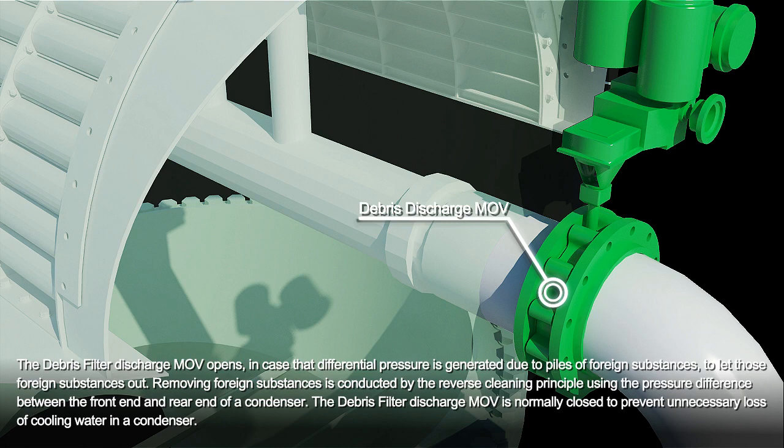Removing foreign substances is conducted by the reverse cleaning principle using the pressure difference between the front end and rear end of a condenser. The debris filter discharge MOV is normally closed to prevent unnecessary loss of cooling water in a condenser.